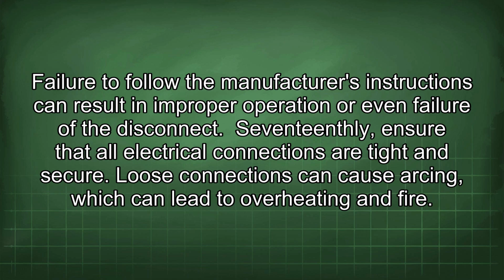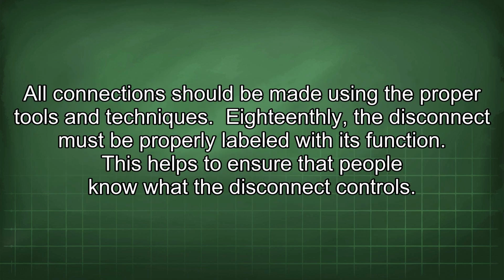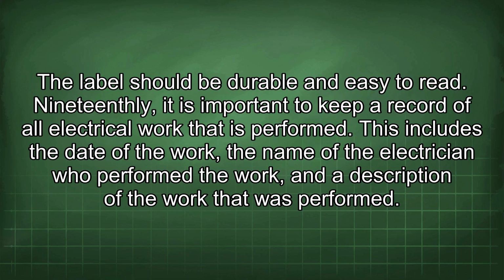17th, ensure that all electrical connections are tight and secure. Loose connections can cause arcing, which can lead to overheating and fire. All connections should be made using the proper tools and techniques. 18th, the disconnect must be properly labeled with its function. This helps to ensure that people know what the disconnect controls. The label should be durable and easy to read.